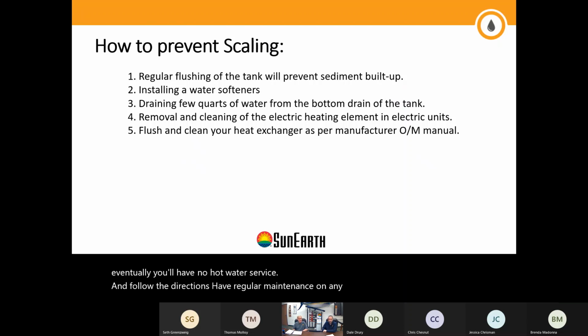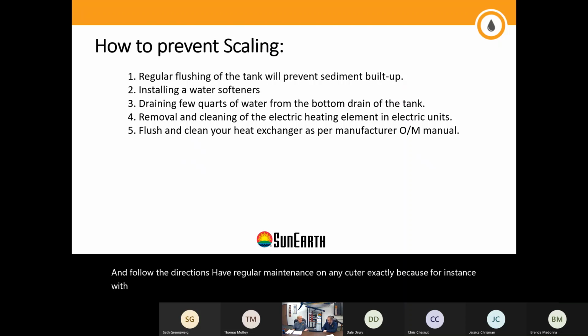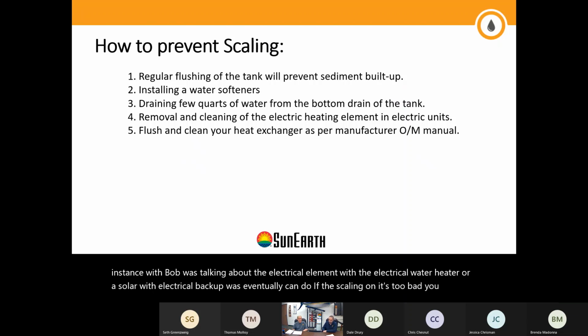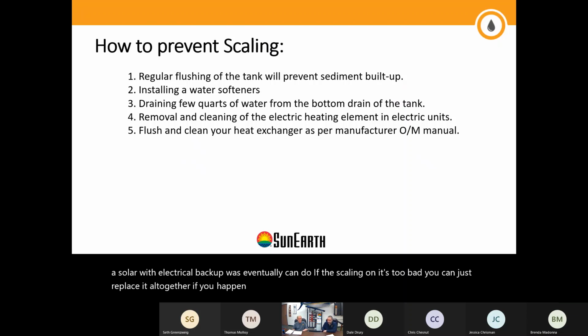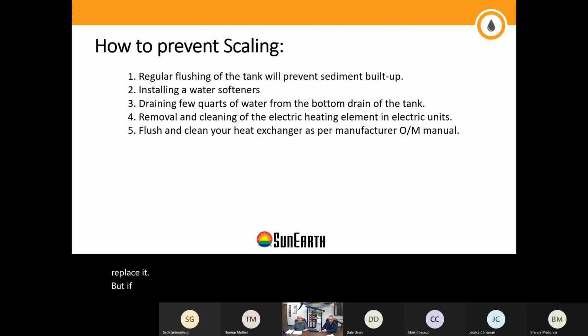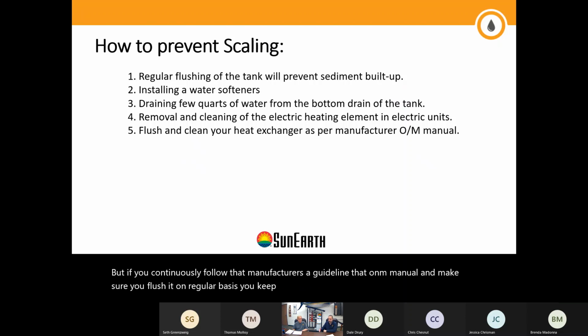Exactly, because for instance, with Bob talking about the electrical element, with the electrical water heater or a solar with electrical backup, what you eventually can do, if the scaling on it is too bad, is just replace it altogether. If you happen to have a gas water heater and that plate at the bottom is all scaled up, there is no changing it. Your best bet is to remove it completely and replace it. But if you continuously follow that manufacturer's guideline, that O&M manual, and make sure you flush it on a regular basis, you keep it clean, that will impact the efficiency of your gas water heater.